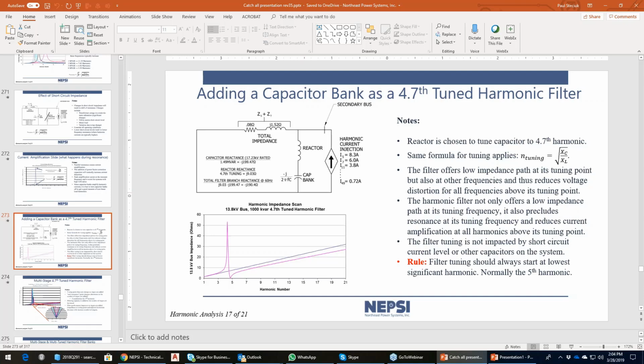Okay, next question. If you use detuned filters, you get more harmonic current back to the source, so it makes handling the harmonics easier. So again, if you're detuning the filter, you're making this filter a less desirable, higher impedance path for harmonic current to flow, so more current flows back into the source. So in a sense, you are increasing the impedance for the fifth harmonic, for instance, into this filter branch. So it is easier, but the question becomes how effective it is.